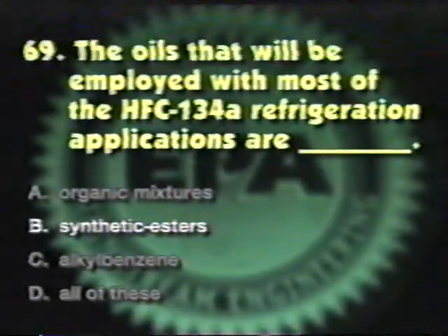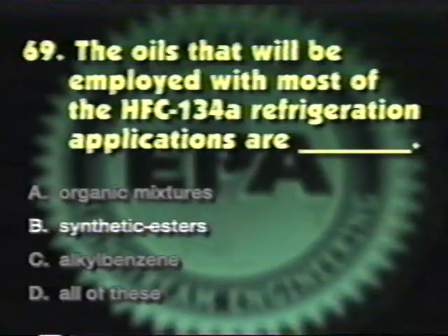The answer is B. Oils that will be used with most HFC 134A refrigeration applications are ester-based synthetic oils, such as POE oils.